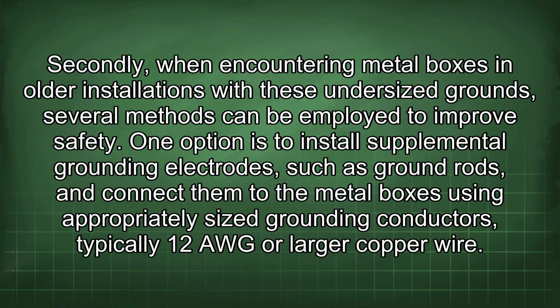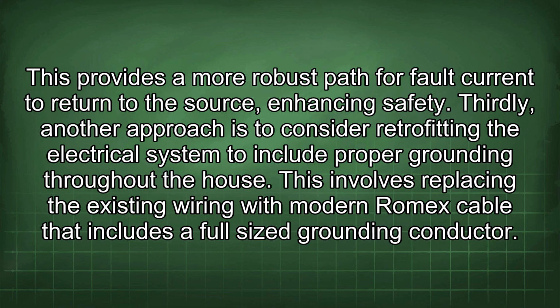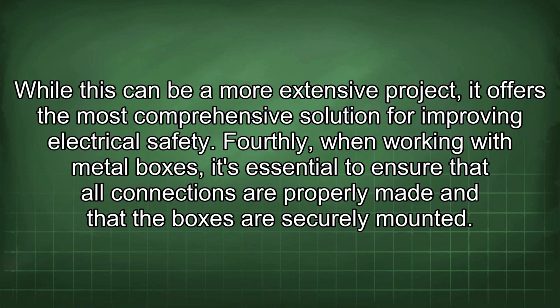Secondly, when encountering metal boxes in older installations with these undersized grounds, several methods can be employed to improve safety. One option is to install supplemental grounding electrodes, such as ground rods, and connect them to the metal boxes using appropriately sized grounding conductors, typically 12 AWG or larger copper wire. This provides a more robust path for fault current to return to the source, enhancing safety. Thirdly, another approach is to consider retrofitting the electrical system to include proper grounding throughout the house. This involves replacing the existing wiring with modern Romex cable that includes a full-size grounding conductor. While this can be a more extensive project, it offers the most comprehensive solution for improving electrical safety.